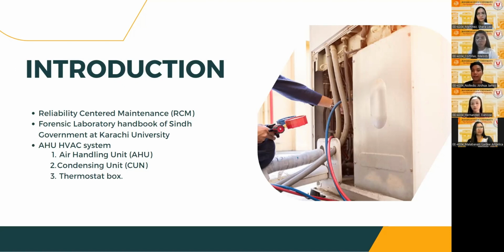facility. 2 critical labs have 100% redundant HVAC systems, 2 air handling units paired with condensing units that are connected to the building management system, which continuously monitors both the system that is running and the one on standby. In case one unit breaks down, it automatically shifts to the other one and vice versa. The BMS system makes sure that the laboratory is available 24 hours a day, even if the HVAC system breaks down.